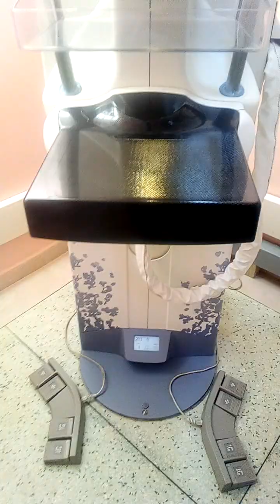We have also incorporated the control panel here, which is basically the main control for the room, and it supplies power directly to all the equipments, I mean the parts which are here. And up here you can see we have the AC. This AC is responsible for cooling the room. The temperatures are supposed to be between 18 and 20 that are set for the proper operation of the Mammo machine. So this is the AVS, automatic voltage stabilizer, that is responsible for stabilizing the power for the AC.